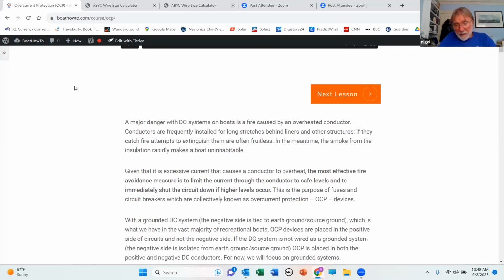So the way the standards are written, it says we need overcurrent protection at or close to any source of power. So what are our sources of power? Alternators, solar panels, battery chargers, inverter chargers, and when they're in charge mode, maybe fuel cells on some boats. However, there is in the standard, this is actually something I got put in there, if the maximum possible output of the charging device, let's say it is a solar panel, is below the ampacity of the conductor. Let's say we put a 10-gauge conductor on there, which has got an ampacity, I can't remember off the top of my head, but maybe 50 amps.